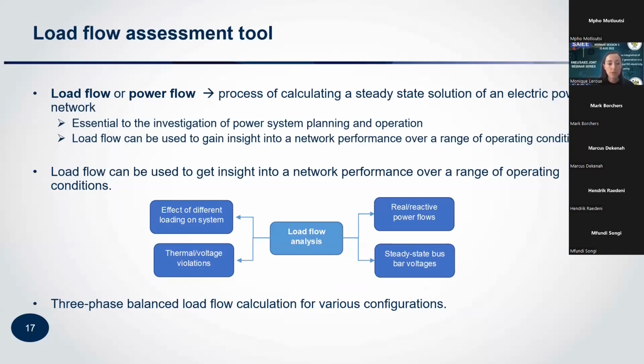As this diagram shows, it will give you the real and reactive power flows through the network, the steady state busbar voltages, the thermal and voltage violations that could be expected on the network for certain conditions or certain plant that's added to your network, and then the effect of different loadings on your system. It is a three-phase balanced load flow calculation for various configurations.